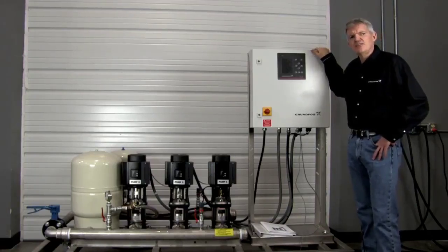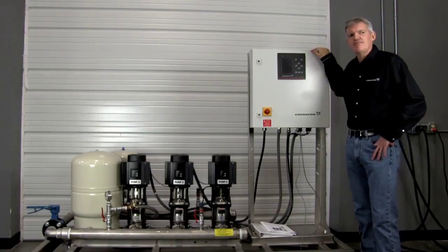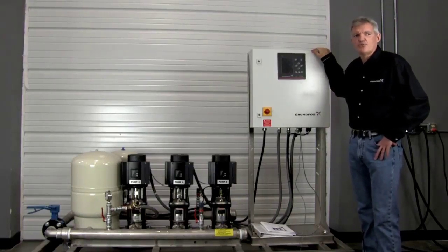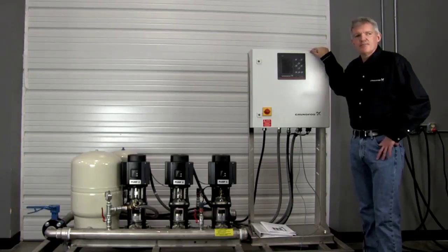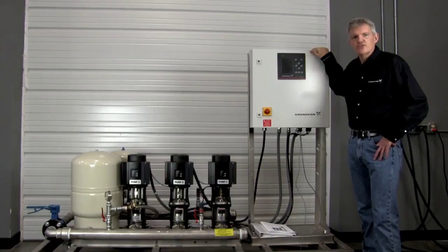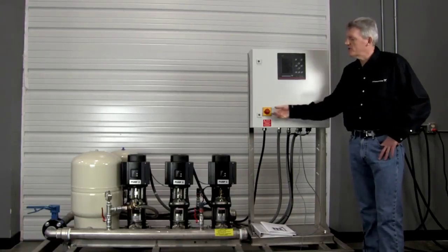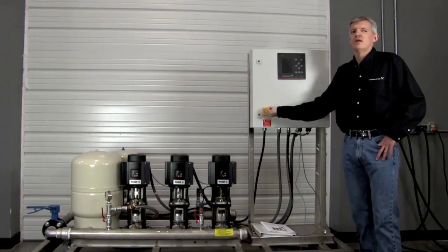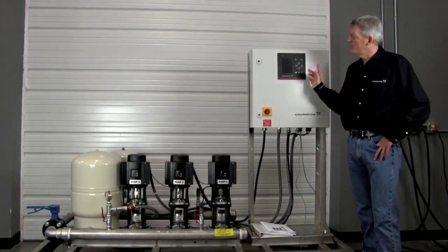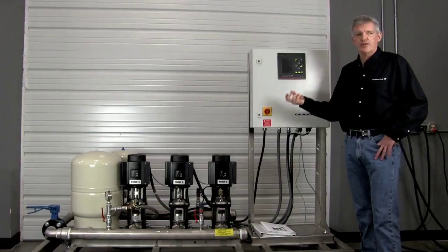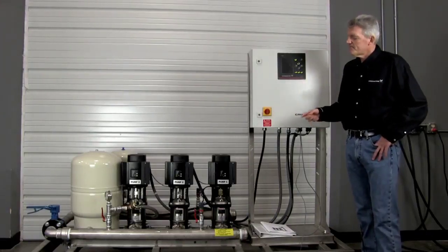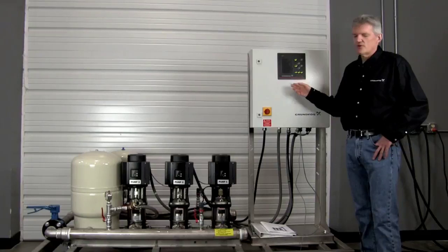This is a Hydro MPC E3CRE 5-5, so it's a system with 3 of our E-pumps on it. When you first power one of these up from the factory, on first power up, it's going to default to the Startup Wizard. Okay, so what we're going to do is turn power on here. It takes about 30 seconds for the CU352 to boot up because it's going to grab the pumps in bus control mode. And so about 30 seconds, this will go to the first screen.